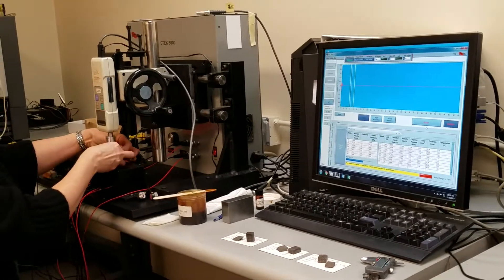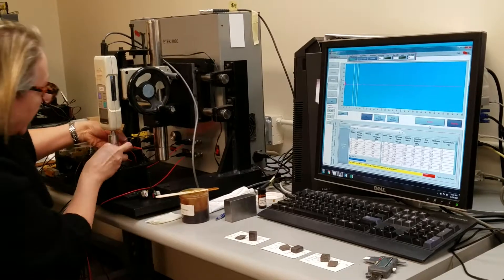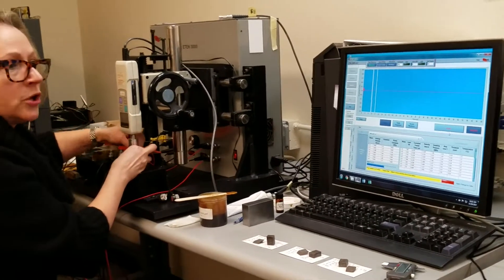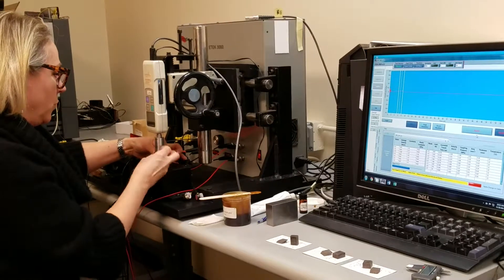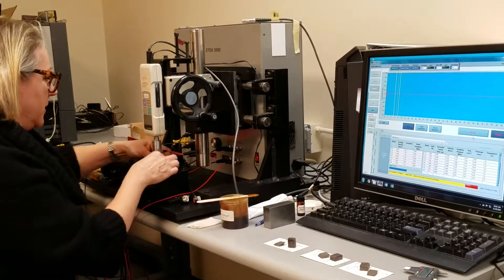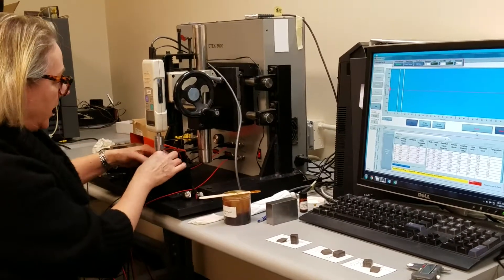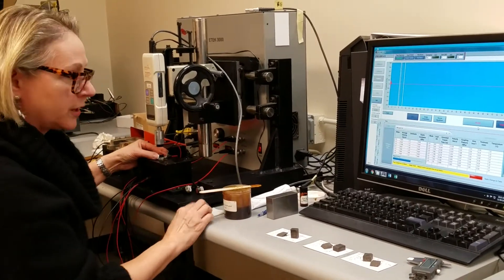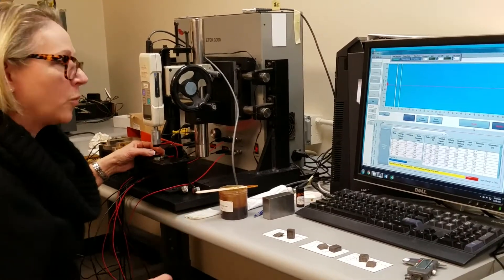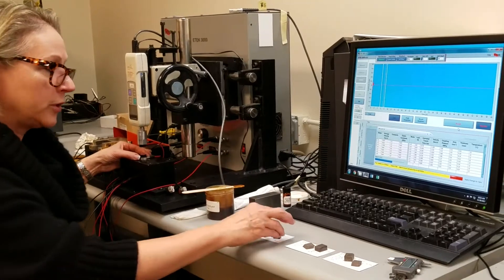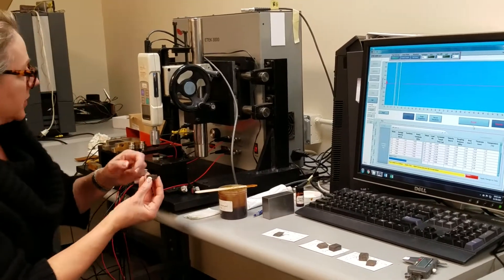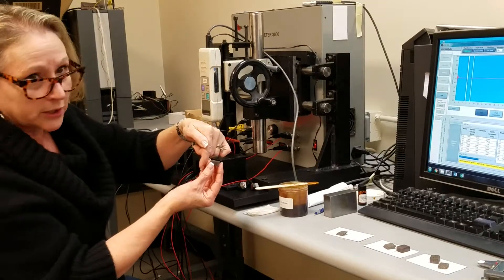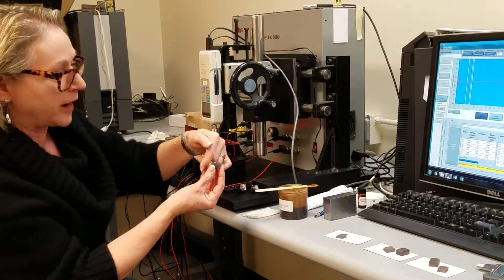With the shear wave measurements and friction materials, it is essential to know where the orientation of the stems of the transducers are. We're going to be doing a 3-2 measurement. That means that the sound wave is going to travel through the thickness of the material, which is the three direction.